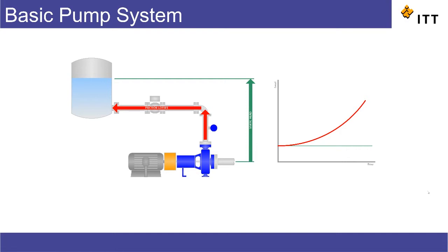So added together, these two make up the system curve, which is the red line on the right. The pump itself is defined by the blue pump curve, which dictates the combination of head or pressure and flow that the pump can produce.